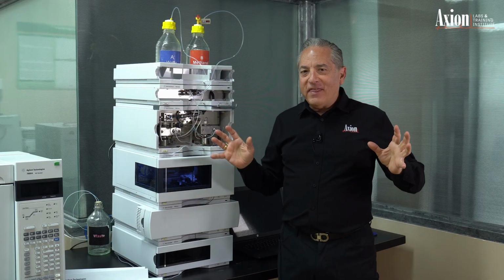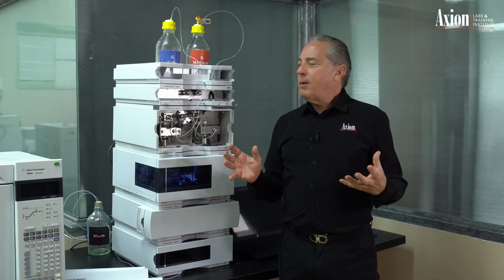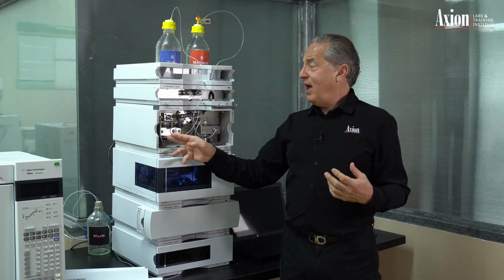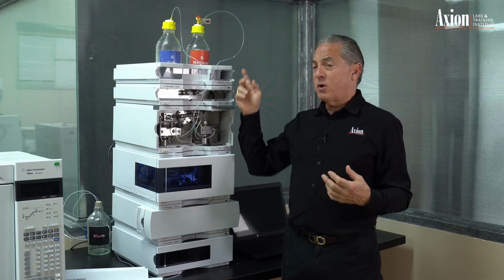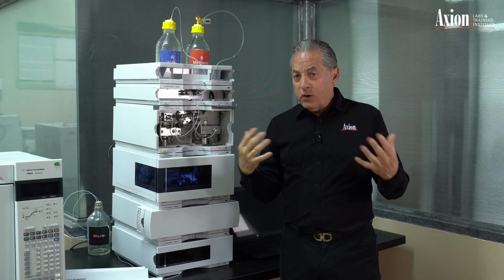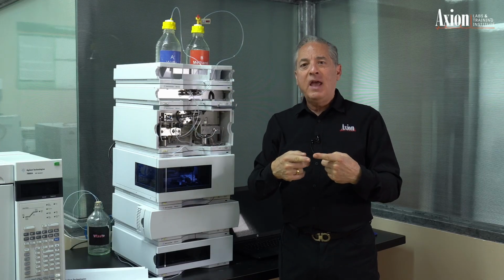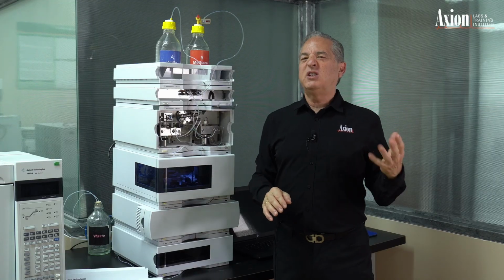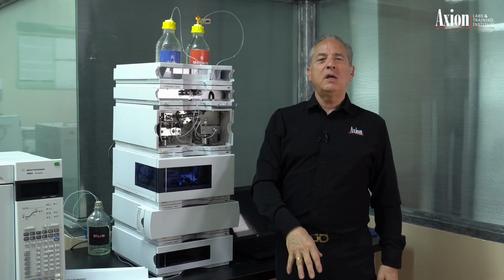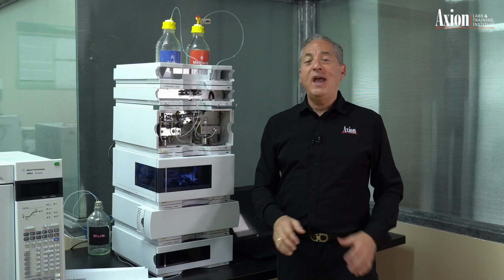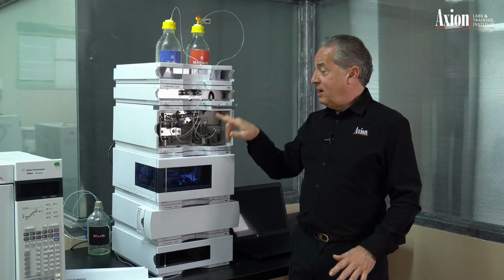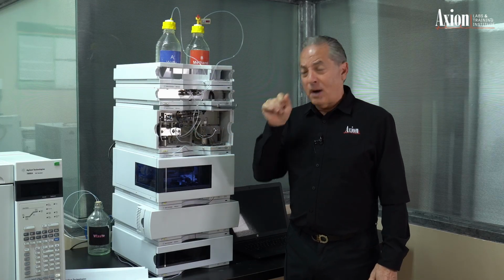So all that I just talked about can essentially be summed up by saying, I've got 2 pumps. Pump A, pumping pure water. B, pumping pure methanol. I can control the 2 flow rates. I can combine the outputs, and I can get any blend I want. You want 0%, you want 0.2%, you want 12.7%, any percentage you want can be blended with these 2 very high precision pumps.